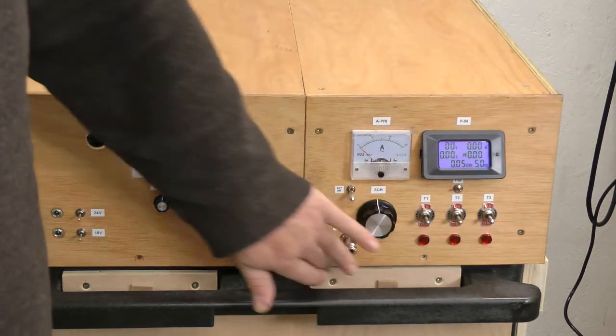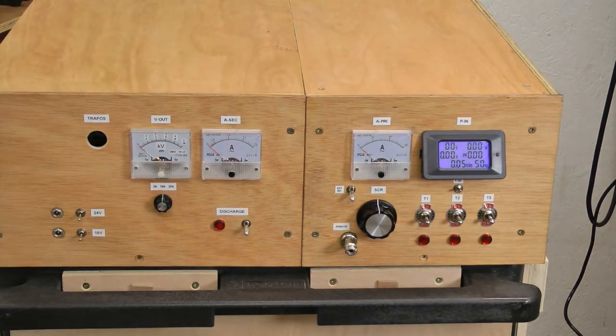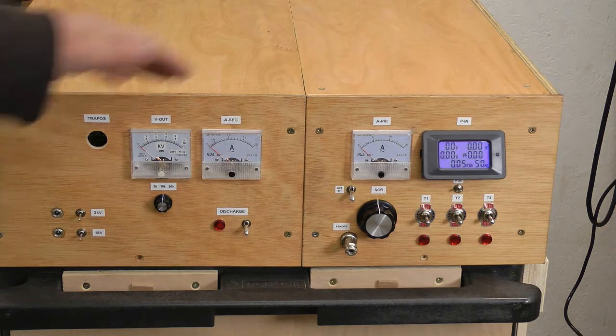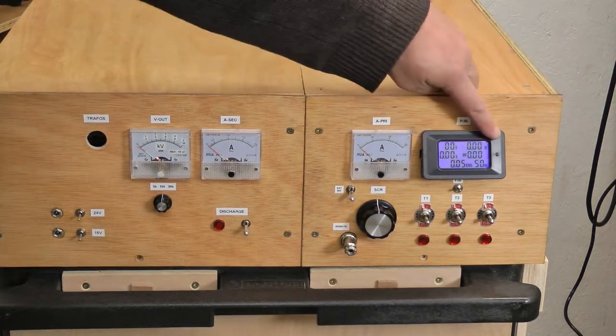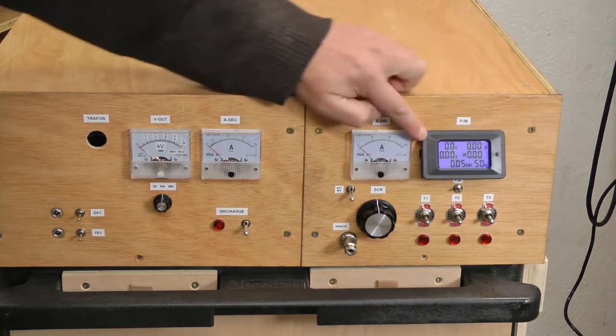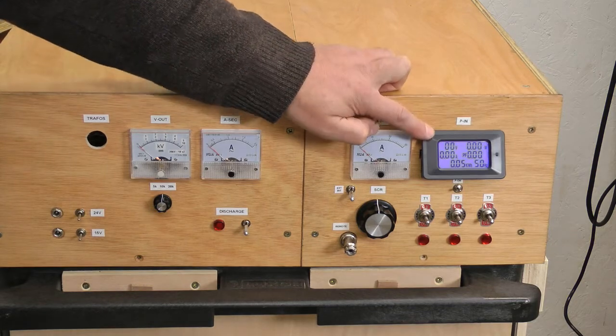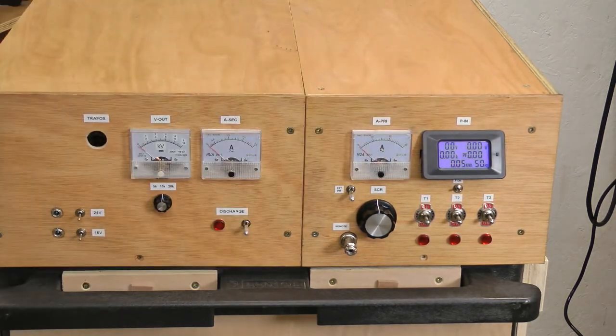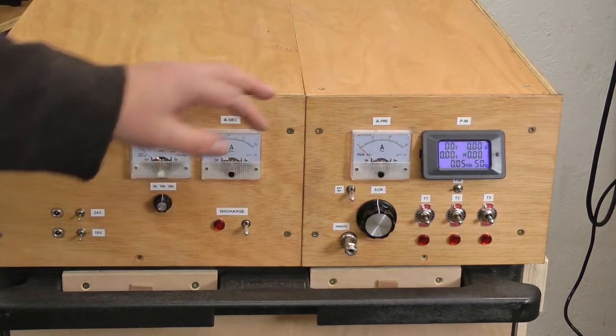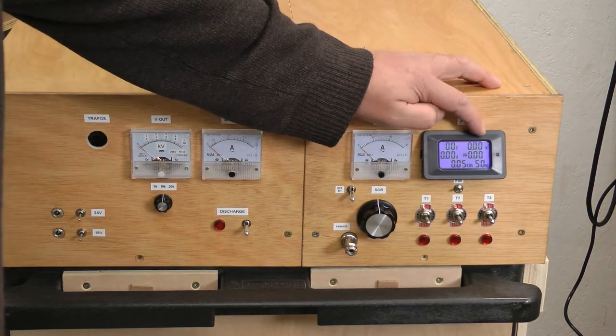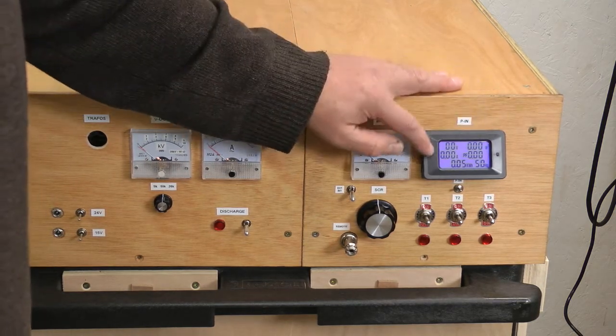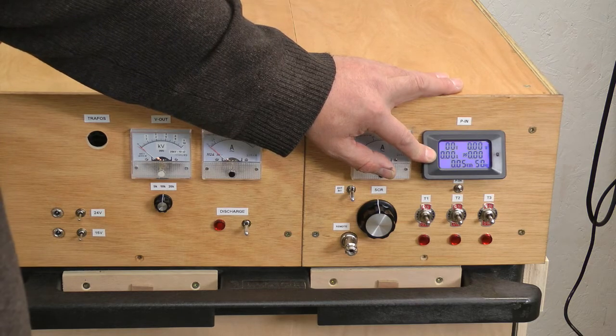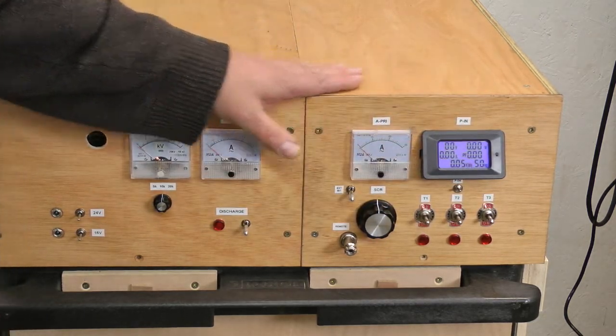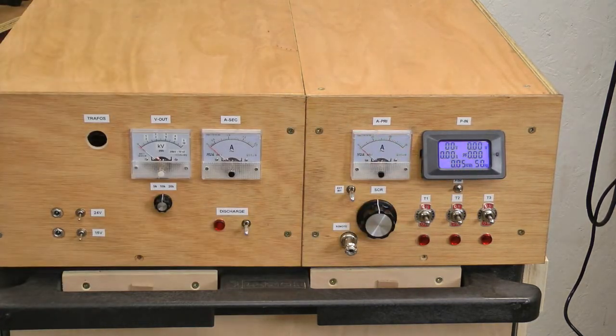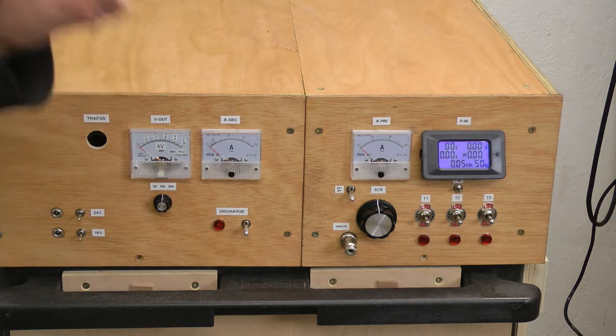This panel here is basically control for the transformers. So it's everything to do with the three transformers. The power that was selected comes round through here, and we have 2 meters. We have a complete power unit here. This is one of those power units that samples the voltage, and it has a current transformer through which either the live or the neutral passes, and then it can calculate a lot of useful parameters like voltage, the consumed power, the amps, the current being consumed, and also showing the power factor, and also the frequency of the supply and stuff like that. So very useful output, gives you all in one summary.